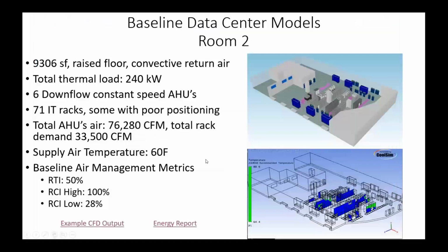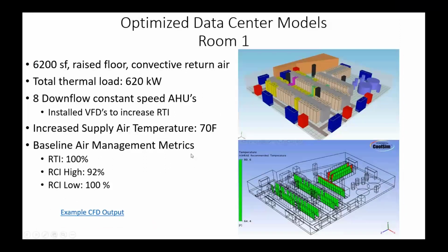So that's room 2. And then room 1, again, I'm not going to go into the CFD detail on this one, but this is optimized now. What you see here is a little bit better representation on this particular conformance plot, over here on the right. Here we have an RTI of 100, which means we've matched perfectly the amount of air being supplied with the amount of air that is required by the racks. So we're at a 1-to-1 ratio.